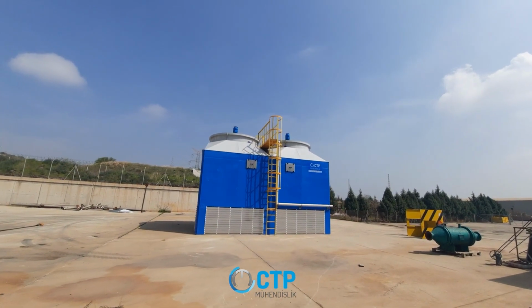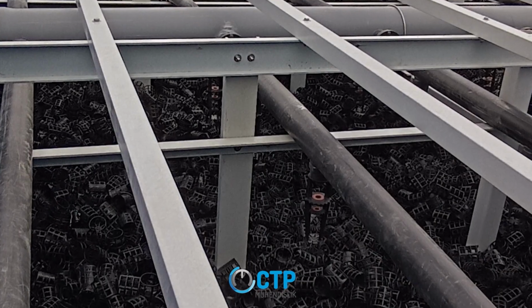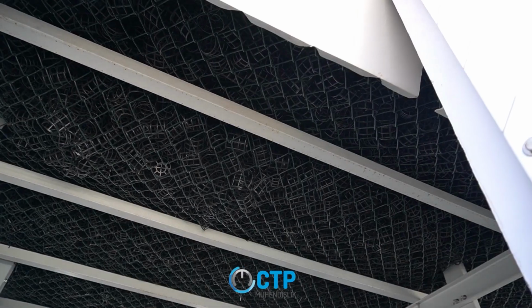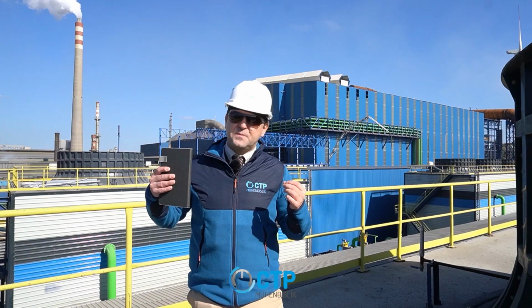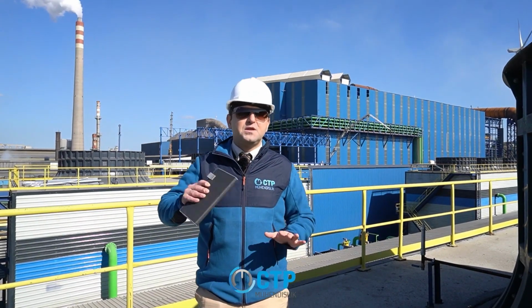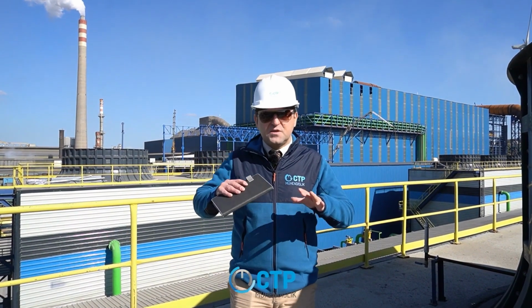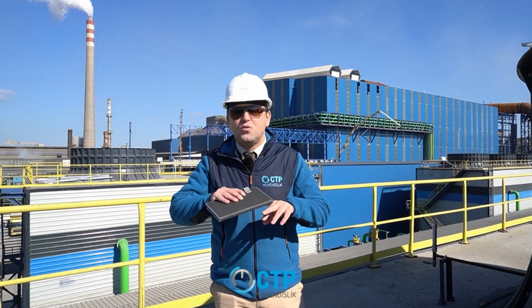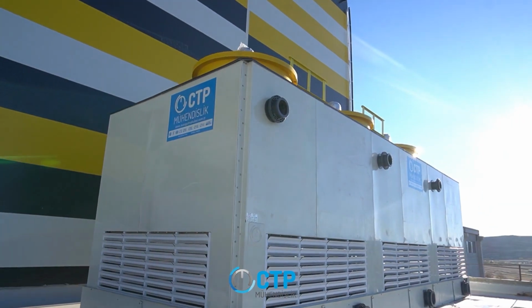Another purpose is to provide surface area for evaporation and physical contact. It also spreads the droplets out, making them a bit more flat. Thanks to that flatness, the surface area in contact with air increases. Wherever it touches, cooling occurs both through conduction and through evaporation on that surface.